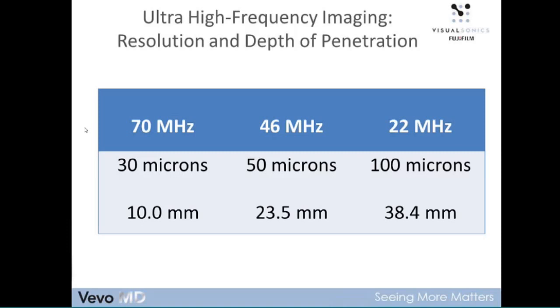30 microns is extremely tiny — if you think of a human hair, which is somewhere between 50 and 100 microns in diameter, 30 microns is smaller than that. The tradeoff, however, is that at 70 megahertz we see only 10 millimeters into the body. As we go lower in frequency, resolution goes down but depth of penetration goes up. There's an inherent tradeoff between resolution and depth of penetration fundamental to any ultrasound system. What we'll be showing you today are exquisitely high-resolution, high-frequency images within the first three to four centimeters of the body.